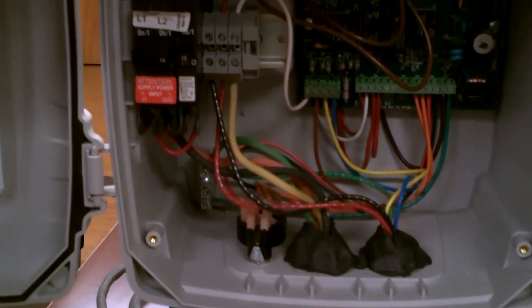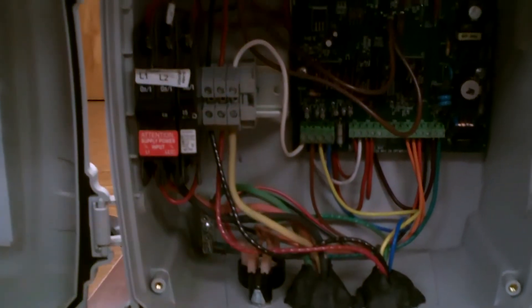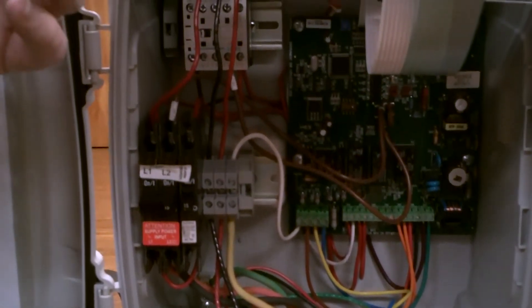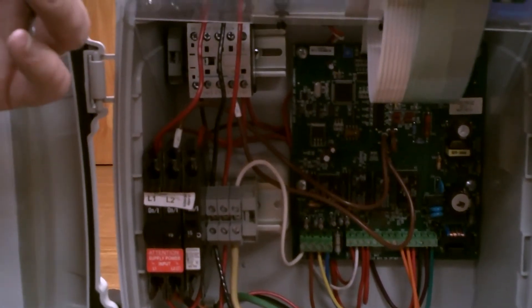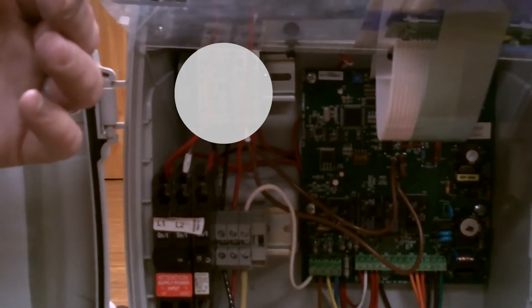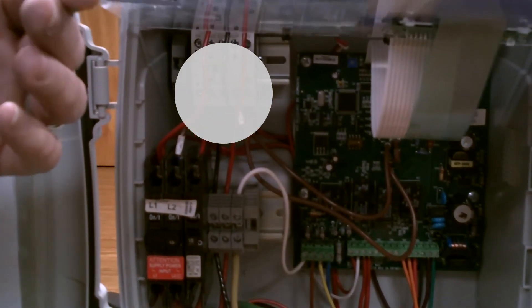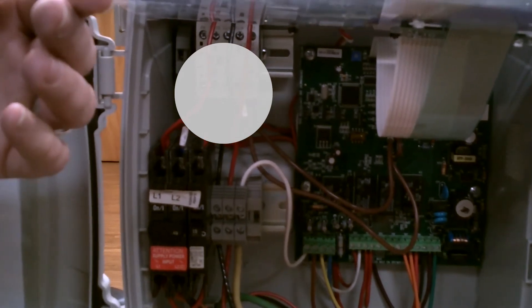Inside this panel, you're also going to see a contactor in the top left-hand corner. The contactor really does nothing but provide power to the pump, allowing the pump to run when the internally housed differential pressure switches close based on a change of water level inside of the station.